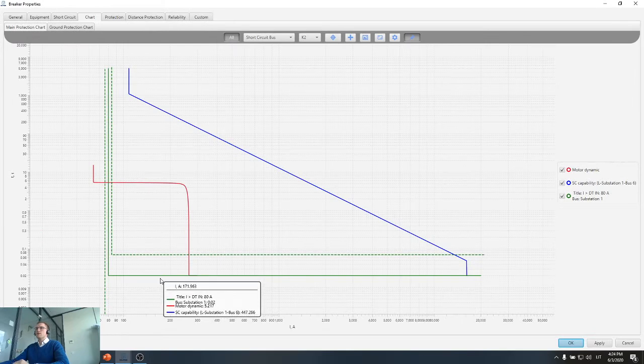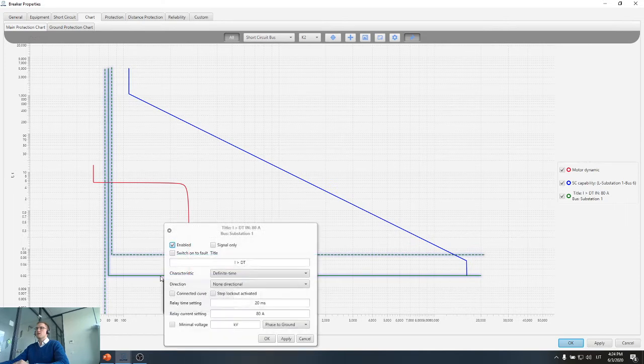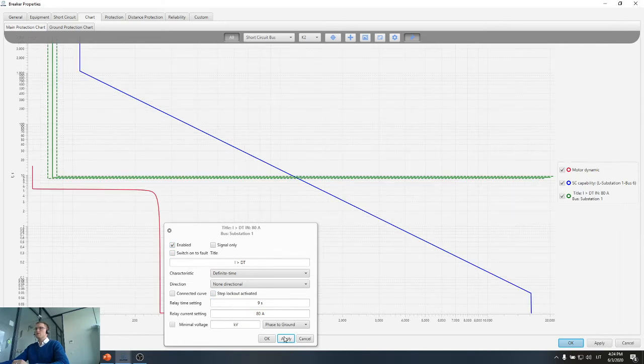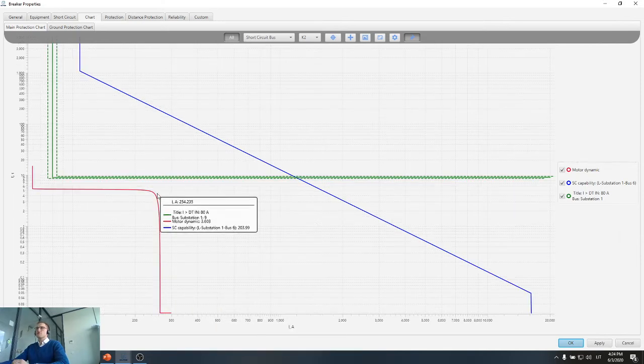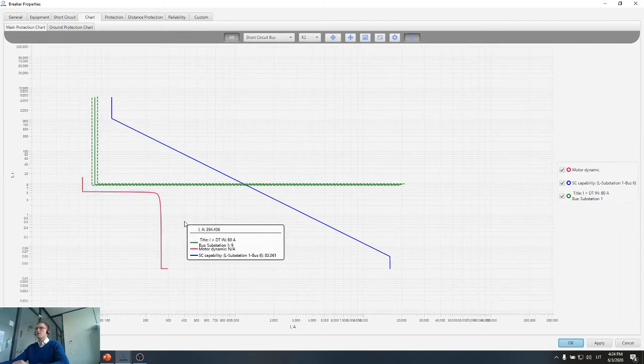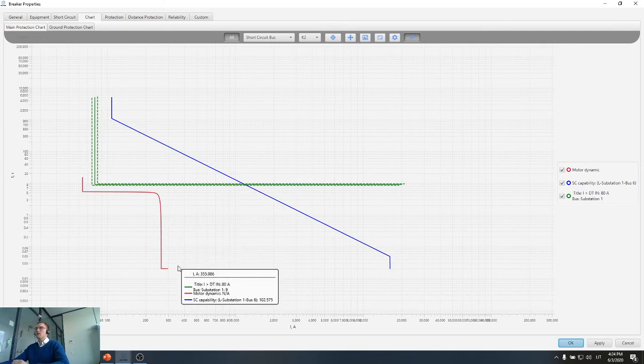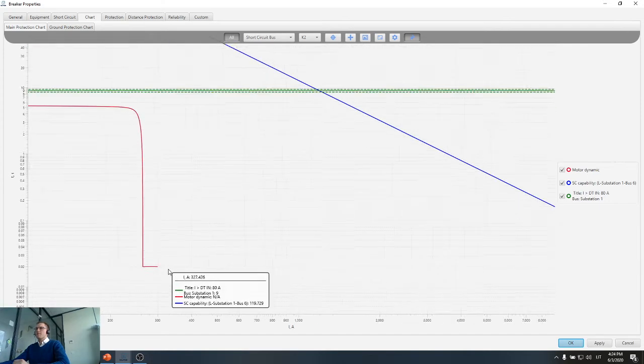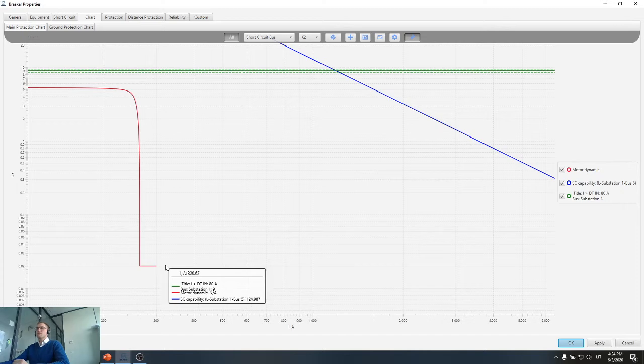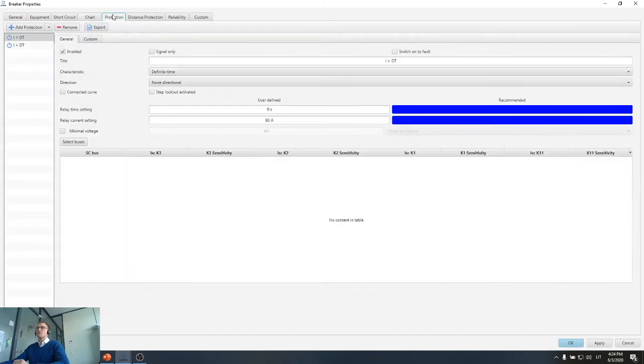time rating for our numerical relay first stage. I can increase, for example, time setting over around, let's say, 9 seconds with some margin. Again, we are not exactly sure. Maybe motor during some of the operations will take more time to launch. Therefore, we have to provide some time margin here as well. Now we would like to add another step, like second step for our overcurrent numerical relay, and I would say that current could be around 350 maybe amps, and time setting could be minimal. I will add the second stage.